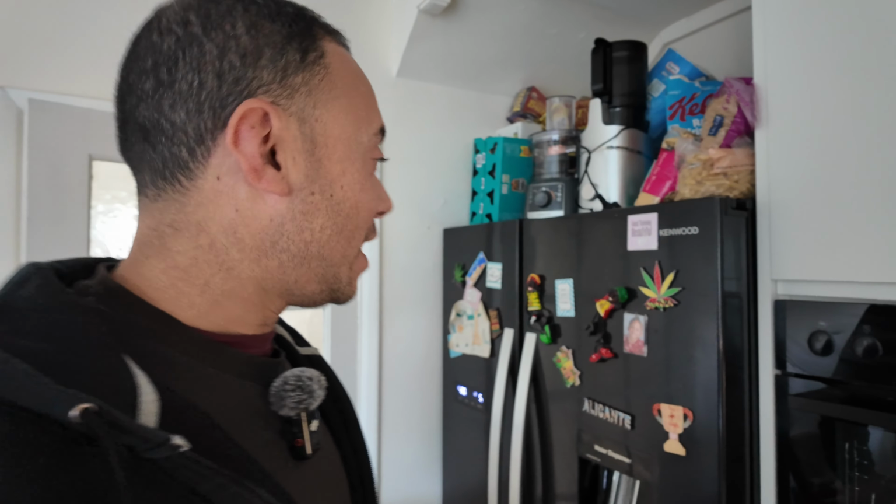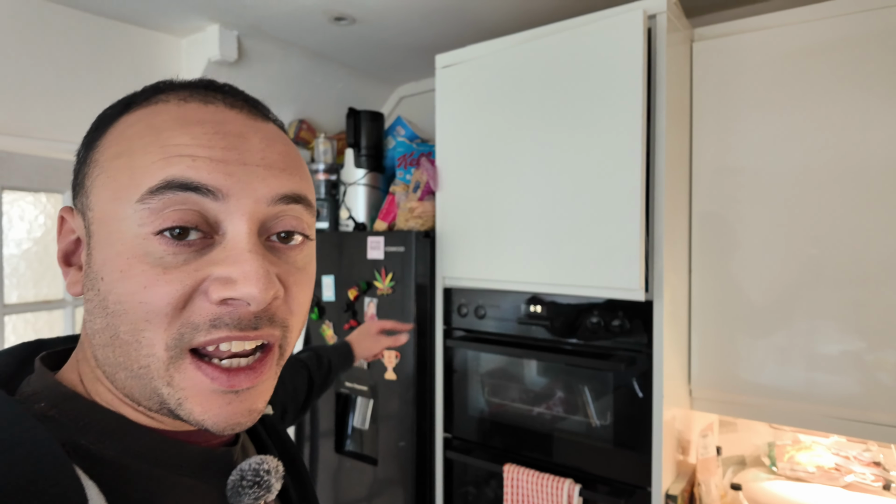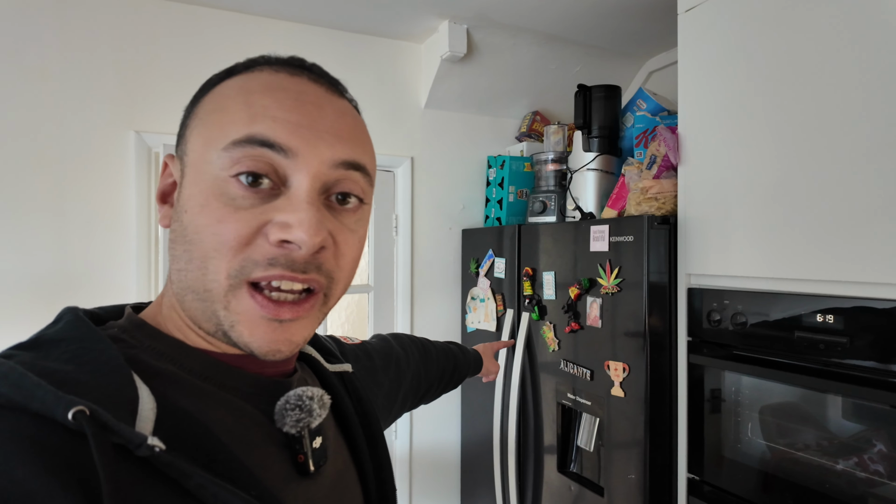Okay, right, so top tip is that when you've got massive items like this, there's a socket down behind here. I never unplugged this at any point. The reason being is that I went to the easy-ish things to get to first. Because then if I unplugged a few things off the circuit and I can get that low reading to clear, then there's no need to unplug that. And that's exactly what happened. I managed to get up to 200 meg ohms. So all was good, and it meant I avoided unplugging this unnecessarily.